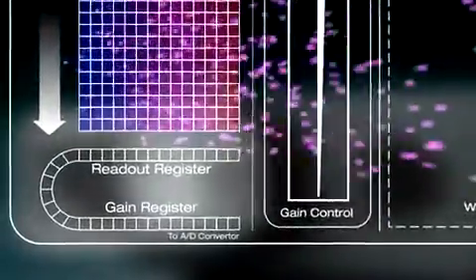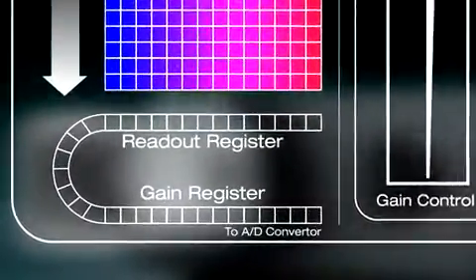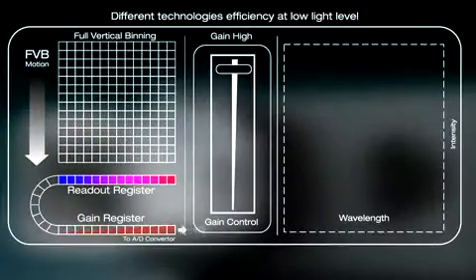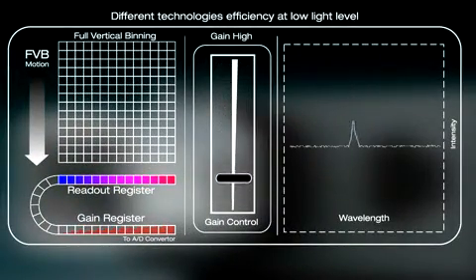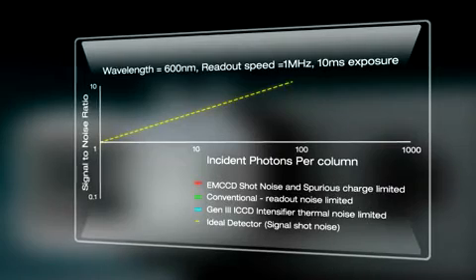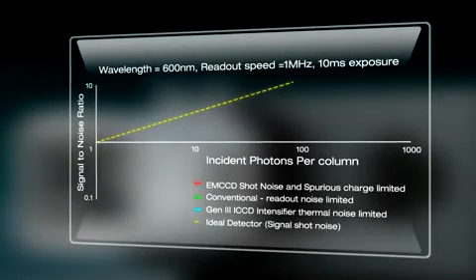For EMCCDs, electronic signals are shifted through an additional gain register, where single photon events can be amplified well above readout noise by impact ionization of up to 1000 times. By doing so, EMCCDs overcome this noise source completely, thus dramatically improving the detection contrast of weak signals.